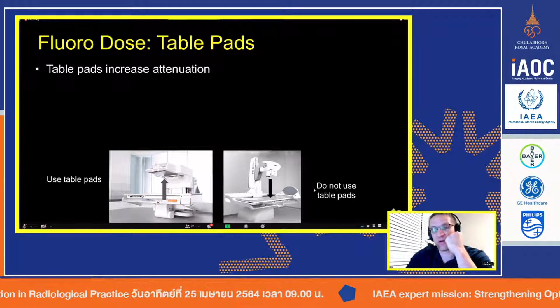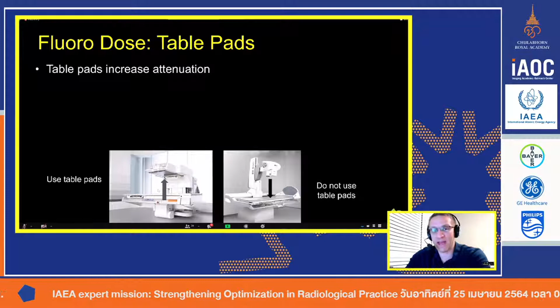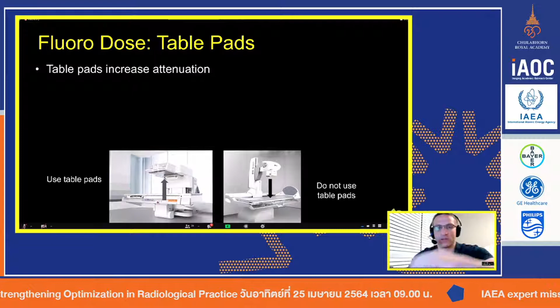if you put the pad here, this machine thinks this patient's thicker, so it will irradiate more. Okay, in this geometry, if you have a pad and a patient, the system still says, oh, I need more radiation to get through, but the pad is between the patient and the x-ray tube, so the pad actually absorbs it. So in this geometry, if the tube is below the patient, you can use a pad. That's okay. It doesn't affect the patient dose. It actually helps it a little bit.